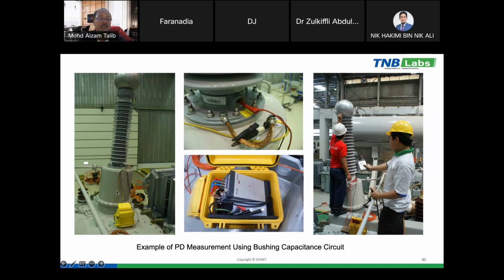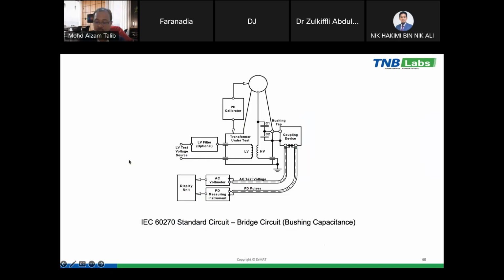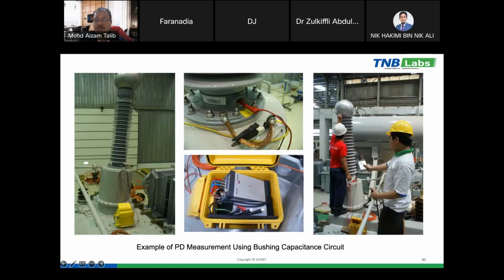Okay, here is an example of the bushing. If we can relate here, this is the bushing, this is the overall transformer. Here is the bushing, the base is the overall transformer, and then this is our quadrupole or matching impedance, where we connect directly to the bushing test tap. Then our matching impedance or quadrupole is later connected to the measuring instrument. And then here we do the calibrations before we inject the high voltage at the secondary side.